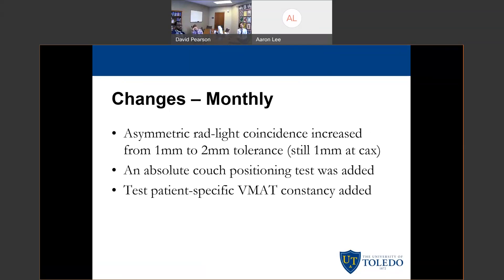Those were the daily changes. In terms of monthly, one thing they changed was the asymmetric light field coincidence — they increased it from 1 mm to 2 mm. This applies for off-axis when looking at a half-field blocked beam. Right along the central axis, it is still 1 mm. The reasoning is that it is very difficult to tell what the light field is unless you have a very precise light-detecting array, which most centers don't have, and even if you do, it probably doesn't have good enough resolution to meet that tolerance.